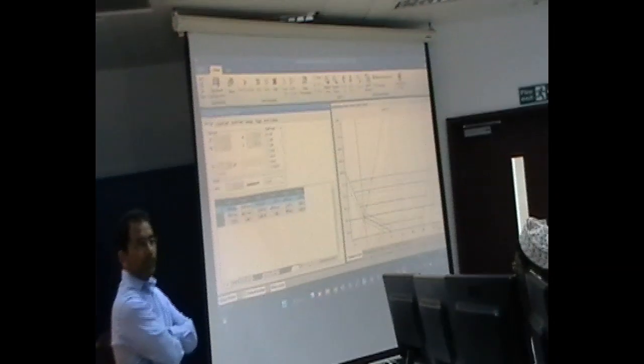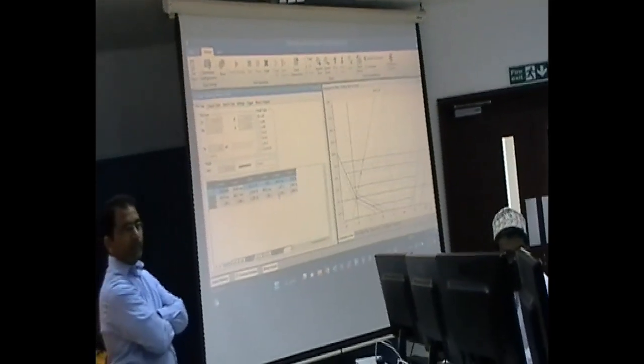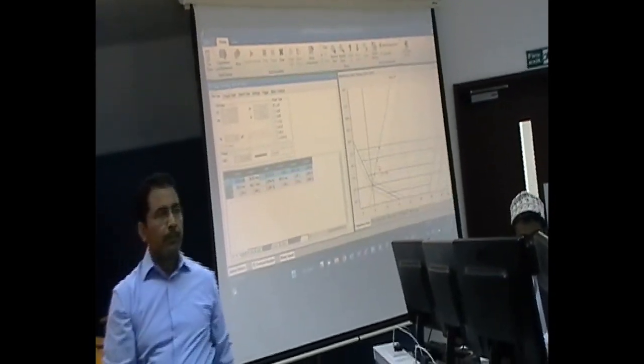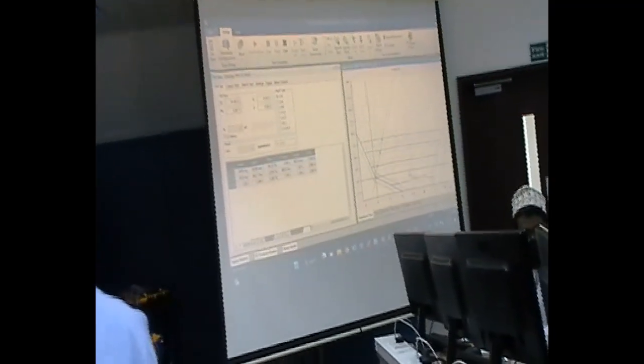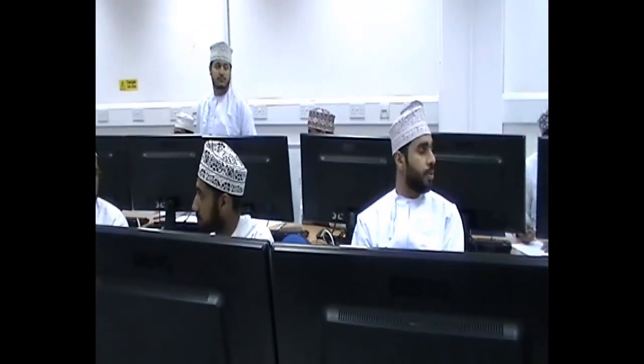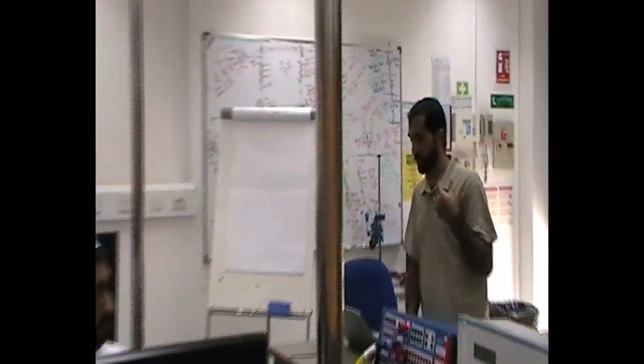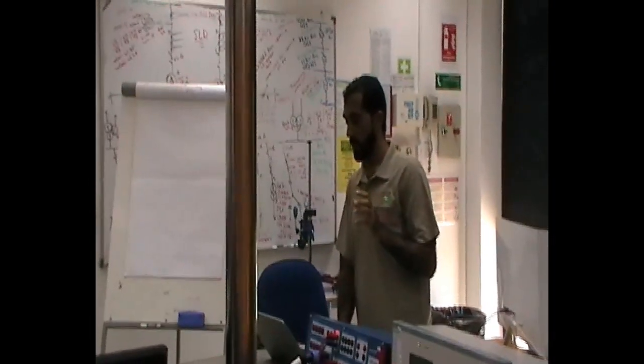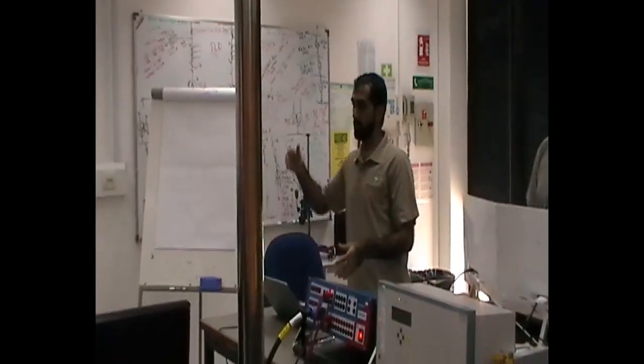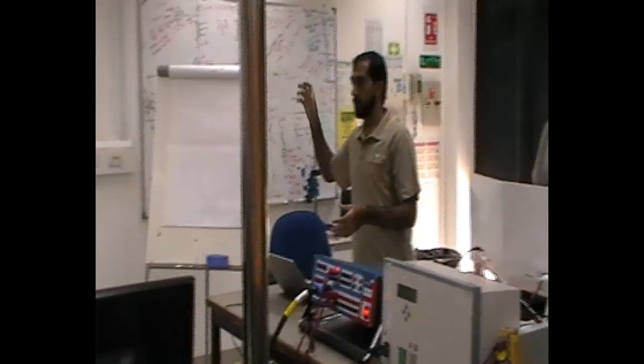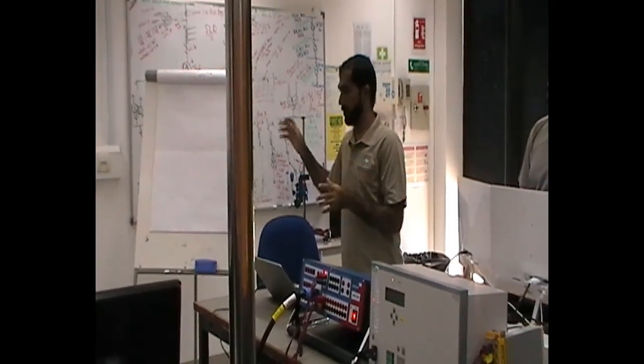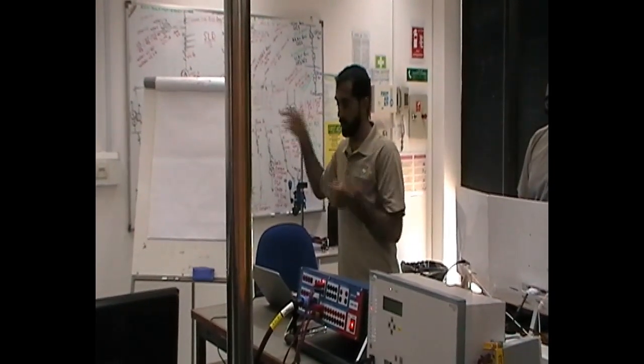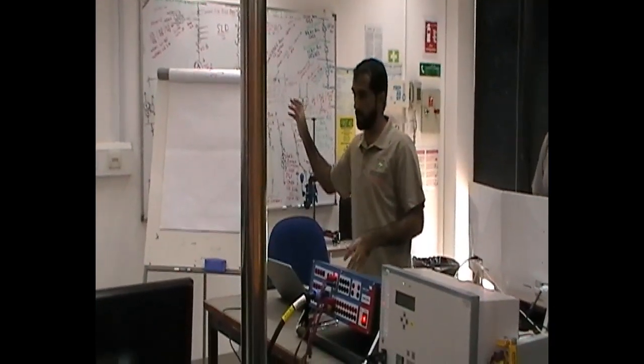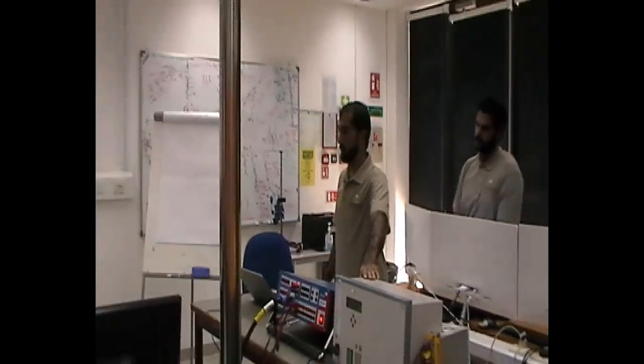Is the time for tripping different as we go far from zone to zone? Zone 1 will only cover about 80% of the line. If the fault is beyond 85% of the line, usually I don't really want to trip if the fault is, let's say, after the line, where we have a transformer. The transformer has its own protection. We have differential transformer protection, and we have overcurrent and other protection in that substation. I'm protecting basically the line with the distance relay.